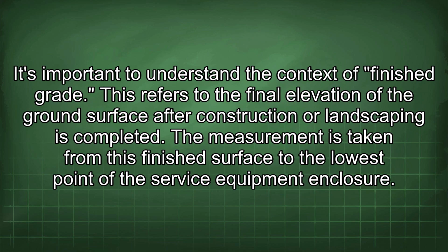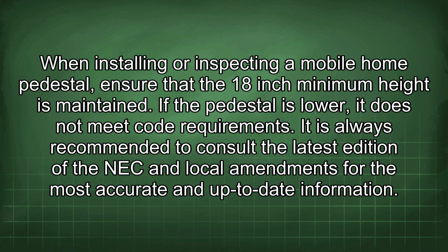It's important to understand the context of finished grade. This refers to the final elevation of the ground surface after construction or landscaping is completed. The measurement is taken from this finished surface to the lowest point of the service equipment enclosure. When installing or inspecting a mobile home pedestal, ensure that the 18-inch minimum height is maintained. If the pedestal is lower, it does not meet code requirements.